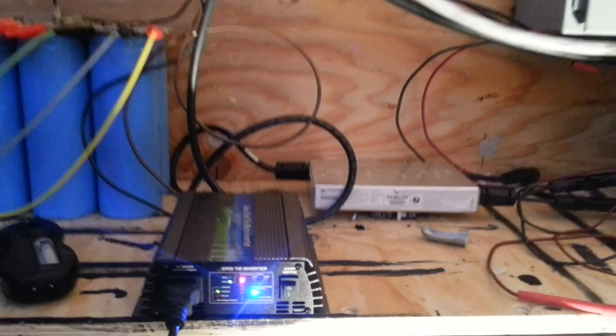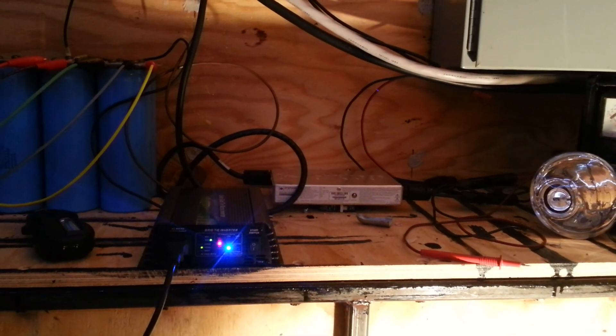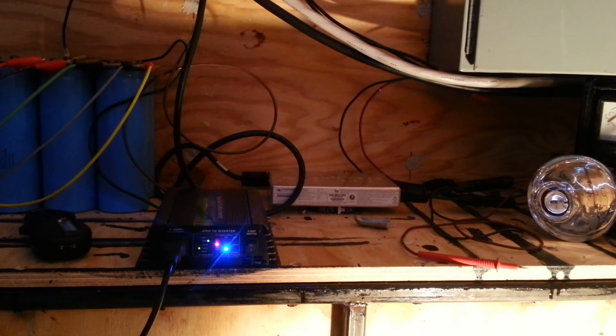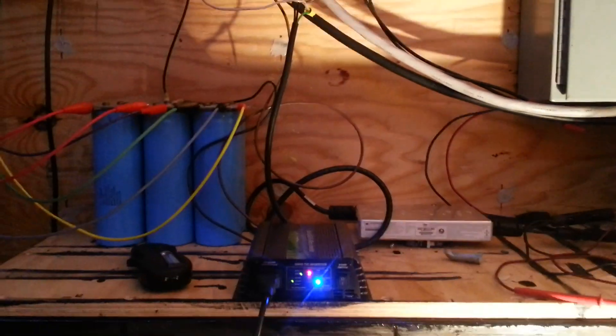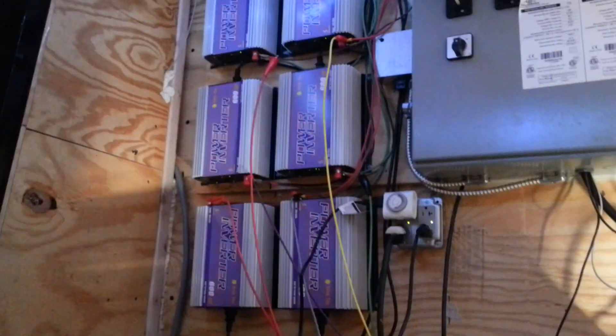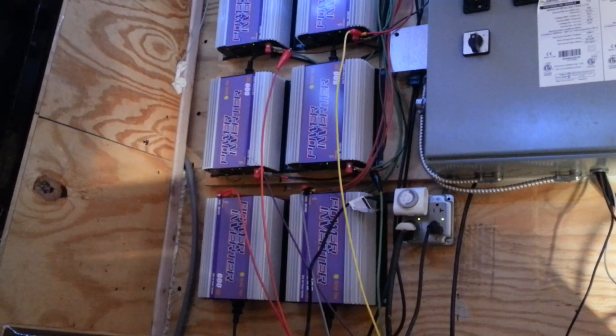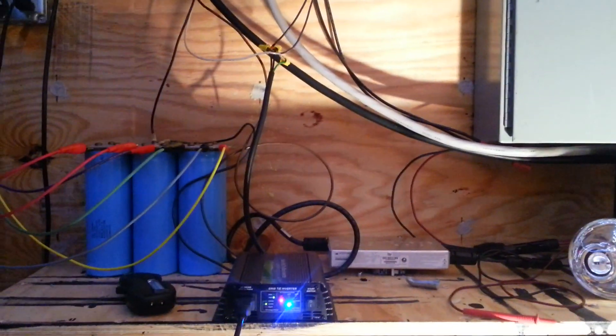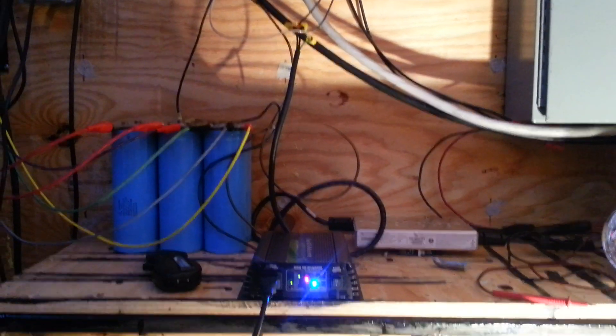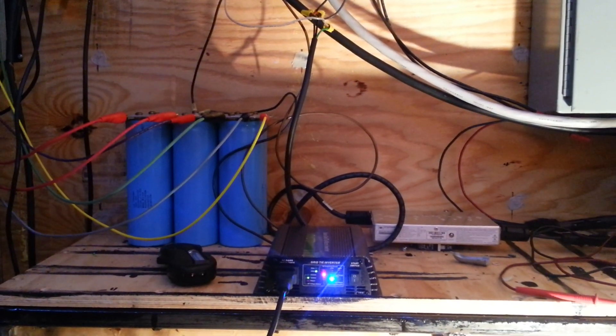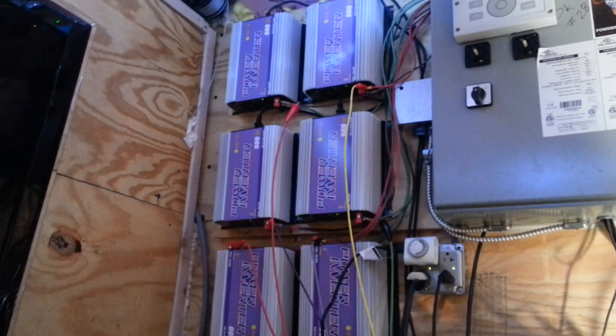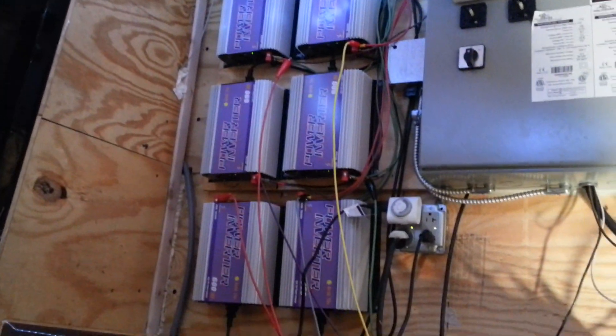The issue I have, what I'd like to talk about today with microinverters, is these solar panels are rated at 420 watts a piece and they have about 60-volt output, 62 volts open circuit voltage. The issue with that is how you can harness that for grid tie. One option is a central inverter where you have one inverter and all the solar panels wired in series. That would be about a 320-volt or 360-volt bus. I tried that and it didn't work out very well because of the partial shading issue. One panel shades and it takes the whole system down. Being a small system like this, that's not the most optimal way to do it. So I wanted to have an individual inverter per solar panel, which is why I went microinverter, and the output's been a lot better than the central inverter.